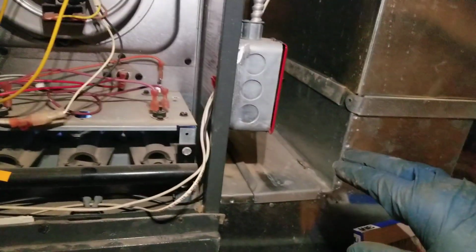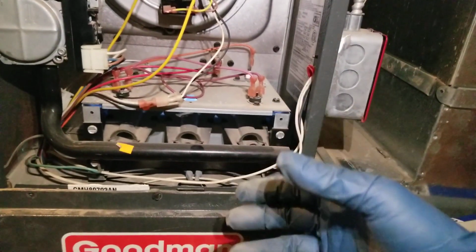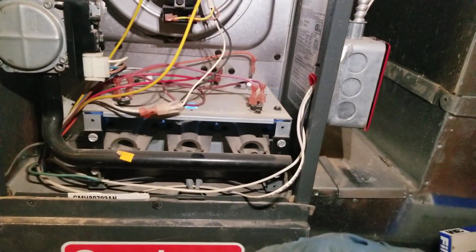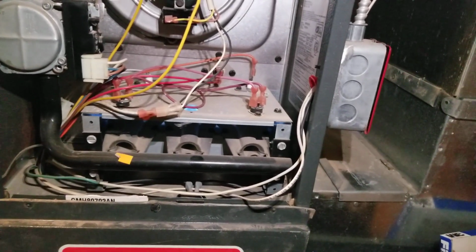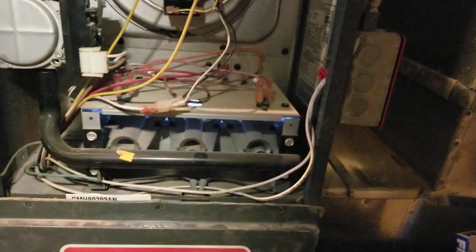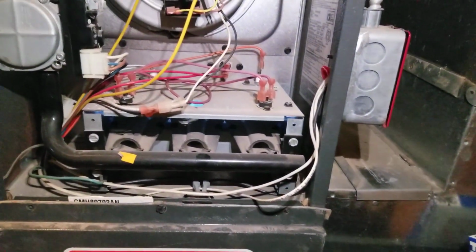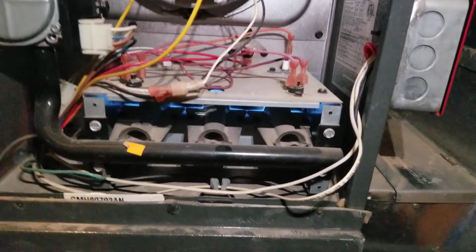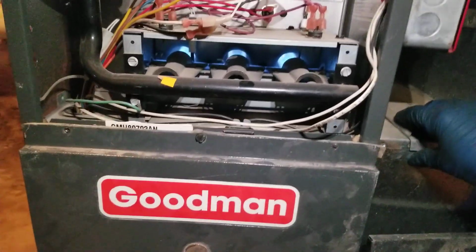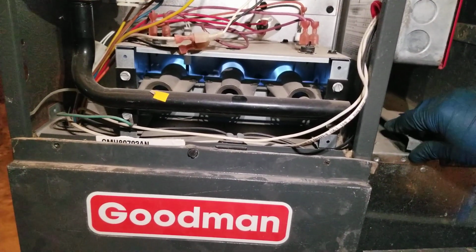It's if you set up the furnace and the only return you have is a 6-inch return, and that's stretched about 15 plus 15 plus another 15, 45 feet or 30, you know, that's not going to be enough for the furnace. So the furnace failed not because of the brand, but because of improper installation.